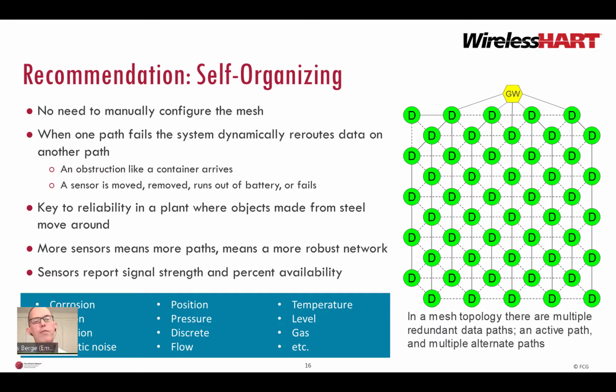Right. You don't have to manually configure the communication paths between sensors. WirelessHART is self-organizing, so the mesh network is formed automatically when the gateway is turned on. Moreover, the self-organizing mesh topology adapts dynamically. If a sensor is moved, removed, runs out of battery, fails, or if an obstruction like a container arrives, blocking the RF signal, the system dynamically chooses one of the other paths, rerouting the data. This is how wireless achieves 99% reliability, even in a plant where the steel obstacles are moved around.